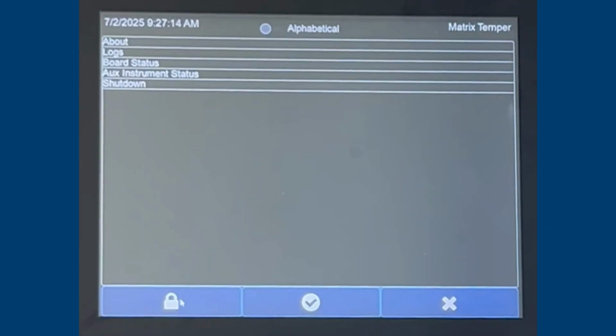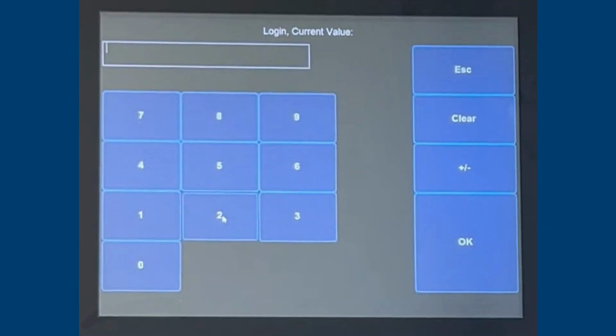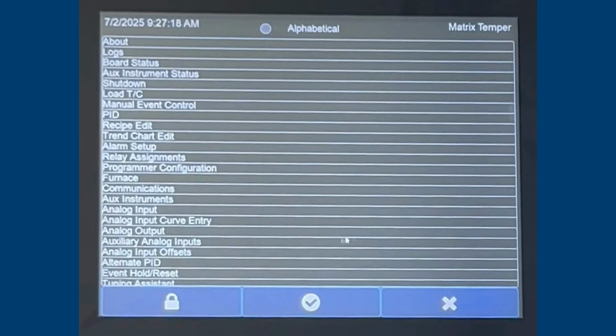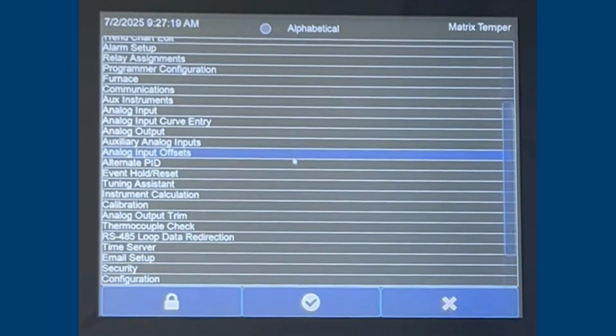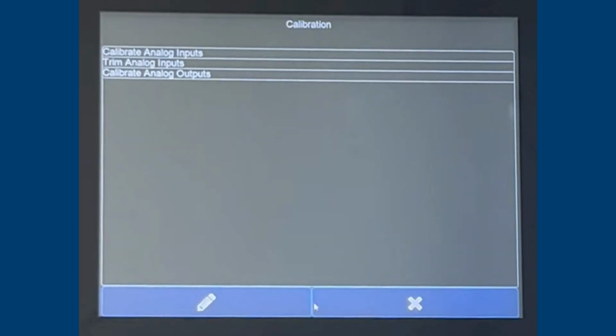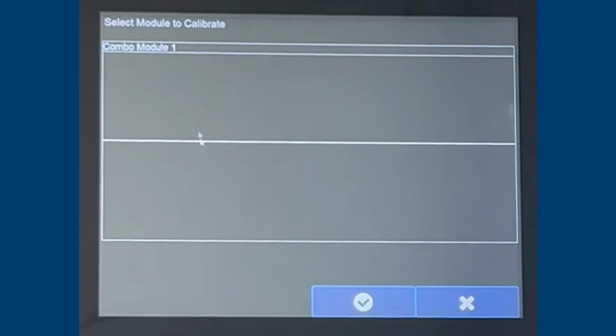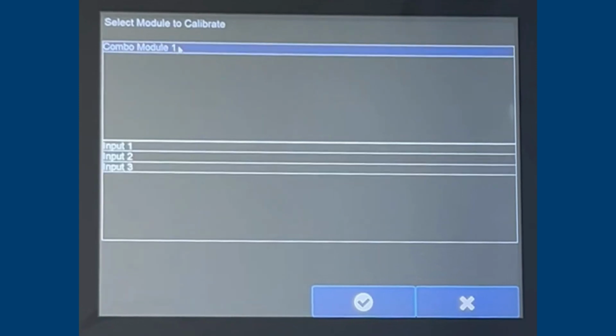Let's start the process by going into the main menu. We will then log in using the number 2. Once logged in, slide down to the calibration option and select it. Then we are going to choose which type of calibration we are doing. We are going to do 0 and span for the analog inputs. Click Edit and select which module if you have multiple available. Select that module specifically and wait for the screen to update.